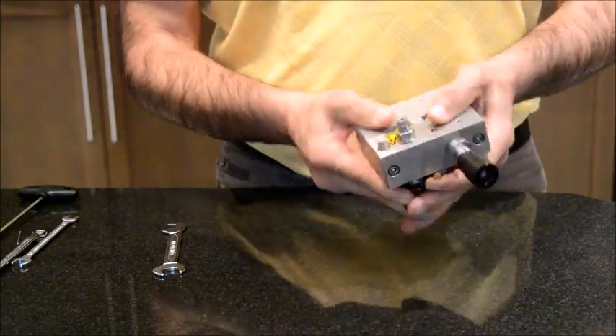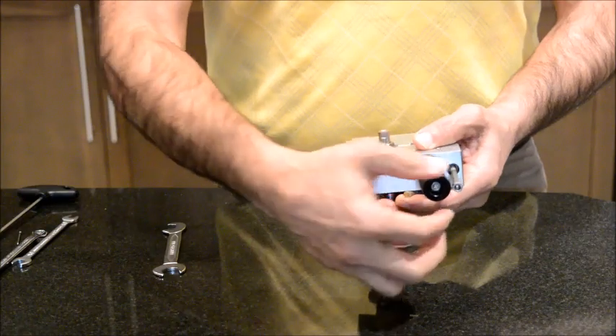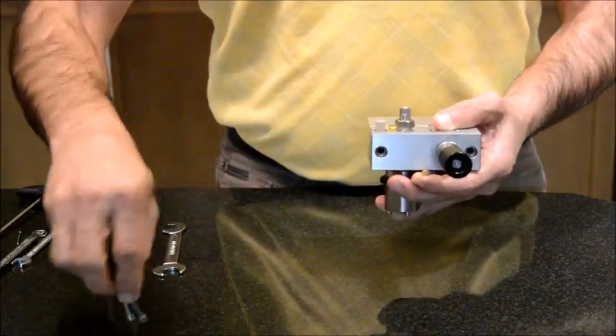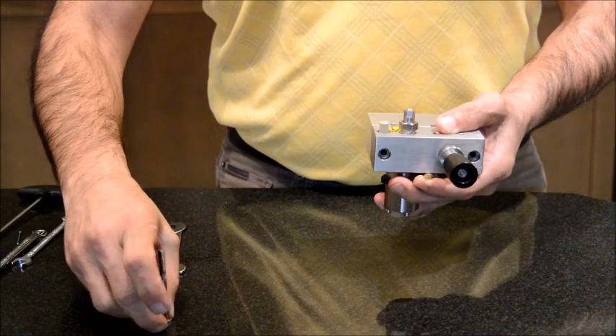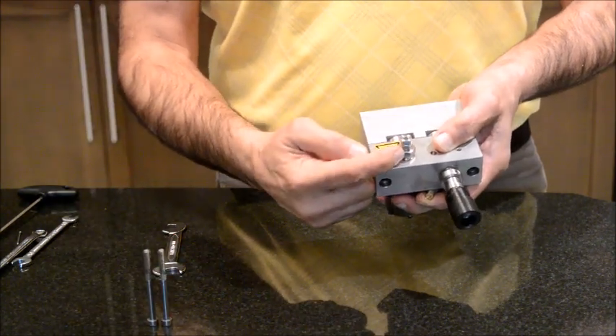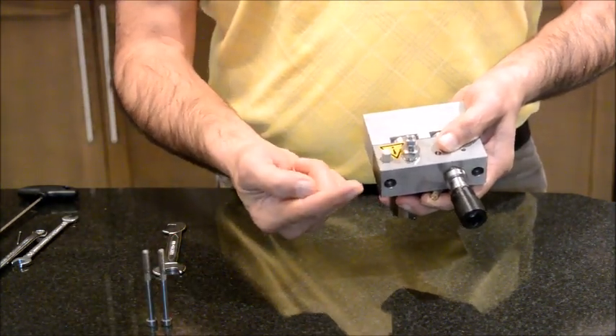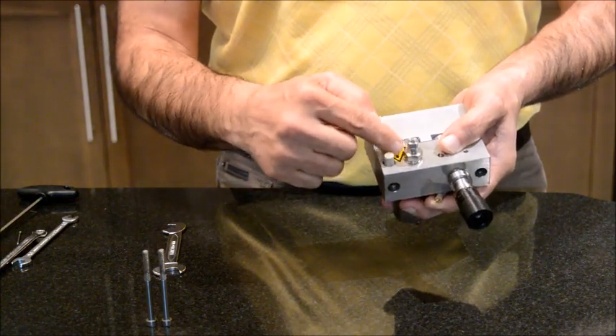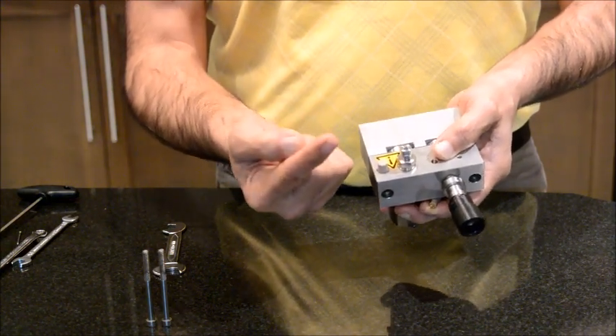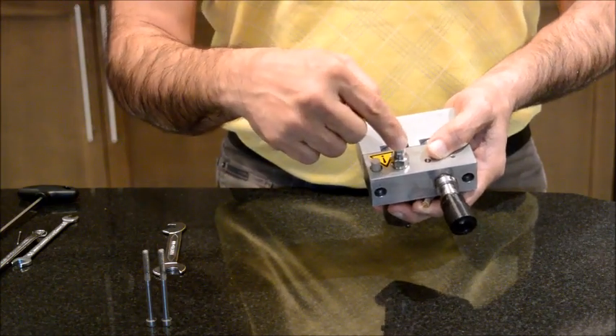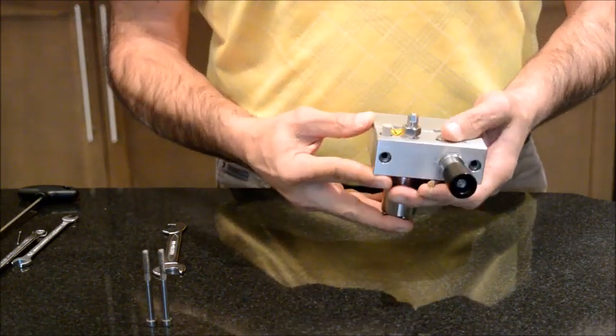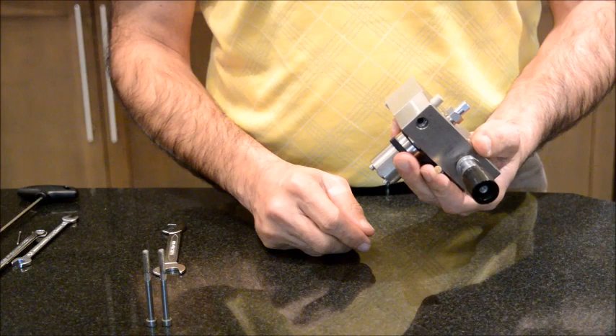I'm going to remove these screws. The other unit that we see on the top, this is a passive outlet valve. What it does is that it will allow the mobile phase to leave the pump head but prevents it from coming back to the pump head due to the back pressure. Now the problems that you may see during your HPLC run that relates to these two components is that your HPLC pump is working but there is no flow into the system or if there is a flow the flow somehow fluctuates.